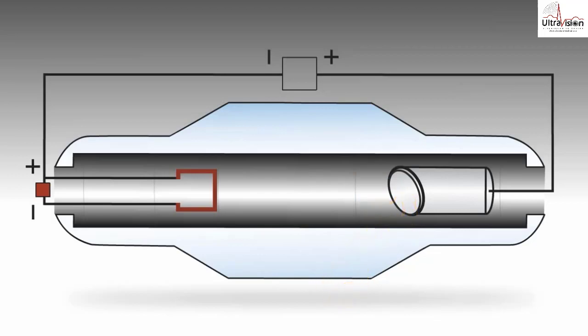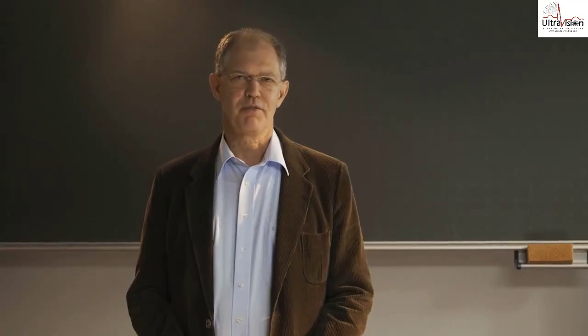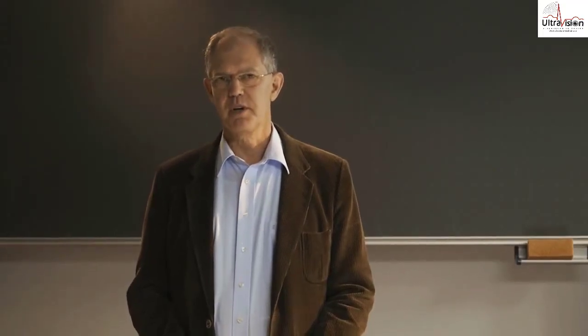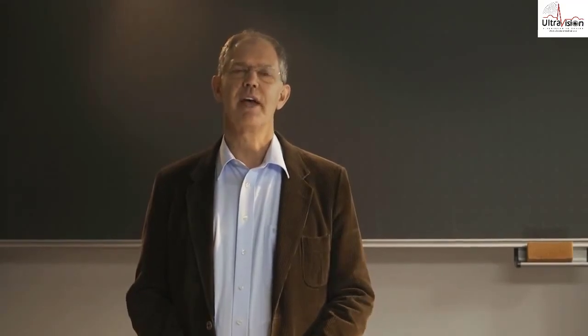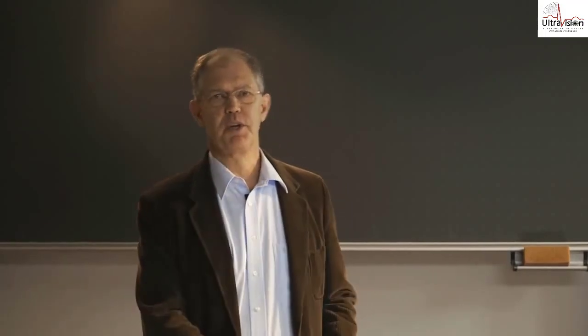Generally speaking, the higher the voltage you use to accelerate the electrons, the faster they crash into the tungsten, and the higher the energy of the x-rays they produce. This means the power of x-rays can be finely tuned for every kind of examination. The part of the x-ray system where x-rays are produced is called the x-ray tube — one of the two main parts of an x-ray system. The other part is called the detector. Taken together, they work just like a normal camera.